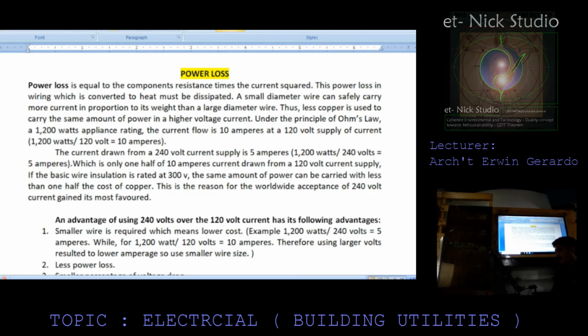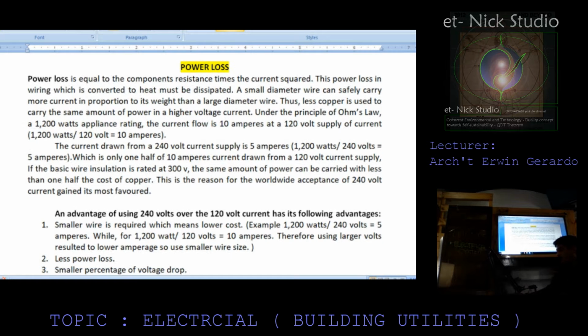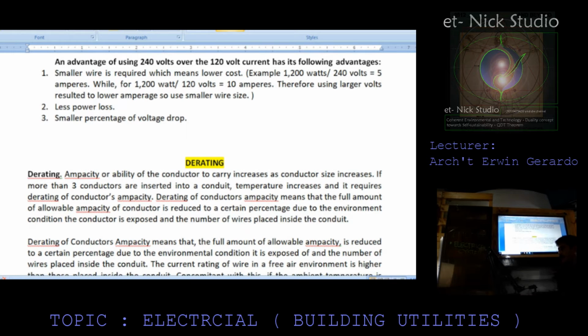If the basic wire insulation is rated at 300 volts, the same amount of power can be carried with less than half the cost of the copper. This is the reason for the worldwide acceptance of 240 volts as the most favored supply. Using 240 volts over 120 volts has the following advantages. Number one, smaller wire is required, which means lower cost. Number two, less power loss. Number three, smaller percentage of voltage drop.